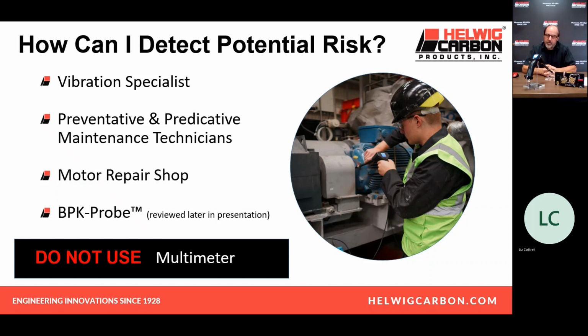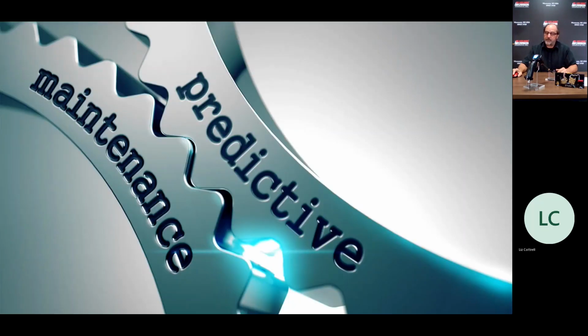You may never use a multimeter. No matter how good your multimeter is, you may never use it to check for bearing discharges. The way the multimeter processes its operating frequency, things of this nature, the RMS output on it, it all deters from an accurate reading. Please do not ever use a multimeter to check for bearing discharges.